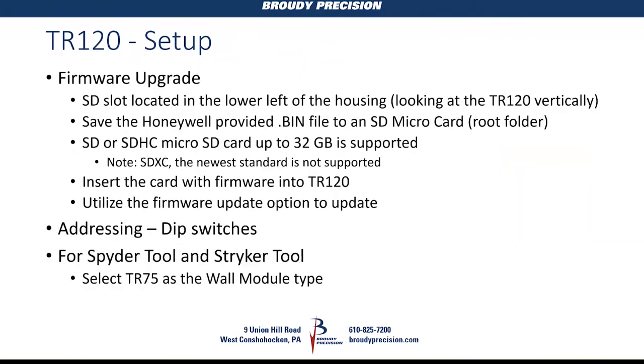When a new firmware version comes out, you put the binary (.bin) file on a micro SD card, insert it into the TR-120's slot, and use the firmware option in the installer setup to update. Addressing is via DIP switches. When using the Spyder or Stryker tool, you choose TR-75 as the wall module type — if someone installs 40 of these now, firmware upgrades down the road would require visiting each unit individually.